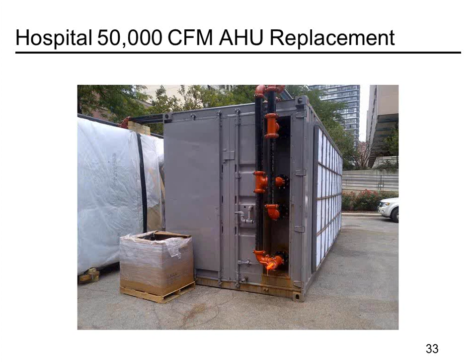Ultimately, the equipment was out there for about 3 months and stood in for the existing air handler while they built a new air handler. It was a fan wall application in the basement, so it allowed the continued operation of the facility while they built the new air handler. Ultimately, with this project, we started working on this probably more than a year in advance before the project actually took place.